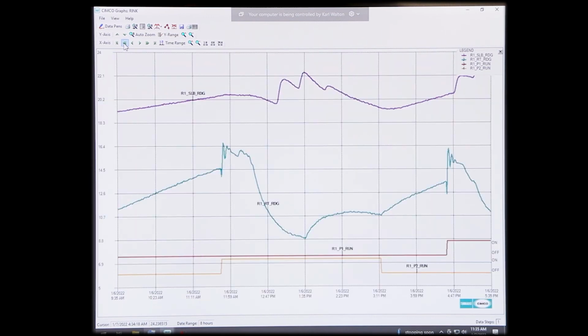Now, here's where I'm going to be able to tell how many floods were made. As we look here, we were under normal run, and somebody said, hey, can you drop the temperature? So the temperature got dropped, and here's a flood, here's another flood, here's another flood. Now this is basically just reading slab temperature. This system doesn't currently have an infrared camera, but you would really be able to pinpoint exactly when they went out, and exactly when the system kicked on, ran, and did everything. And you can see how the system started and then started to respond and return temperature reading. Again, you can look down here on the bottom and see that P2 was online, and how long P2 was online during that time frame that you did that.